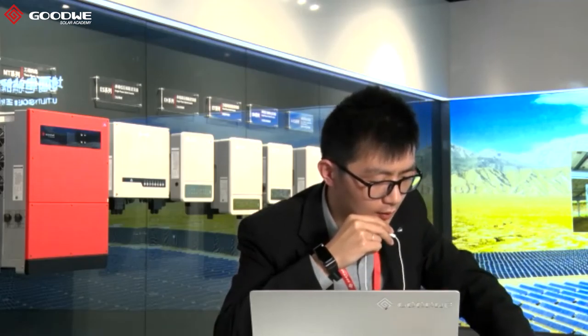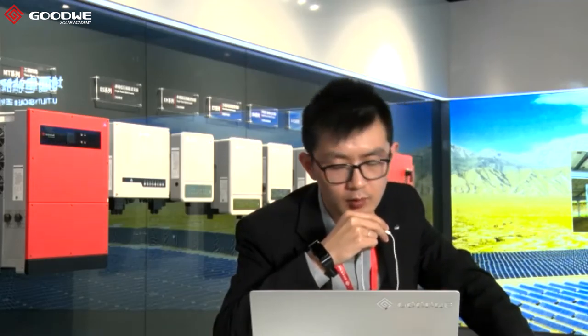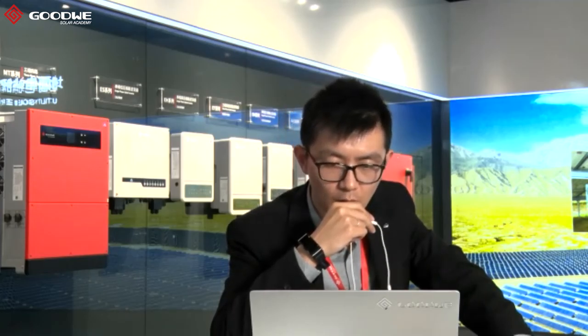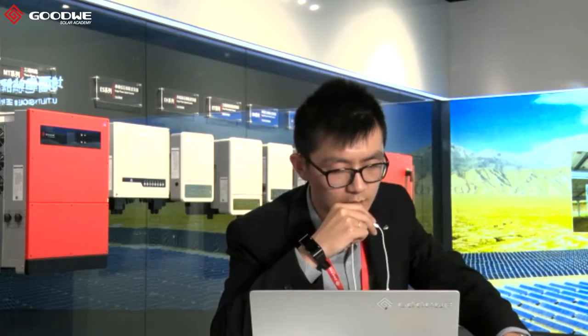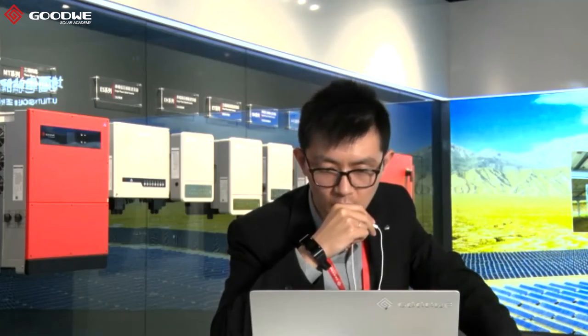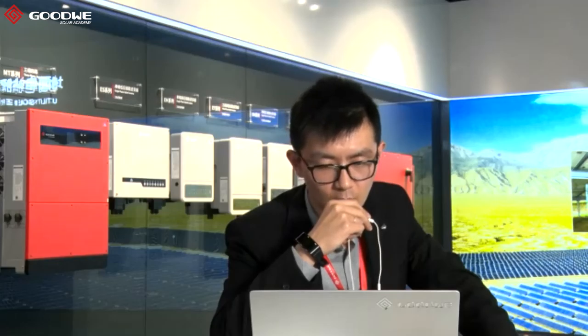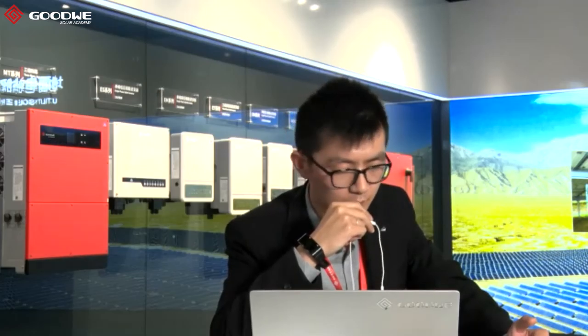The next one is, is the aging test done on full load or something else? In our aging room it is 45 degrees, and it's a full load operation. For example, if the inverter is 50 kilowatt, the inverter will output 50 kilowatt continuously for 8 hours in our aging room. Okay, so that's all. Thank you.